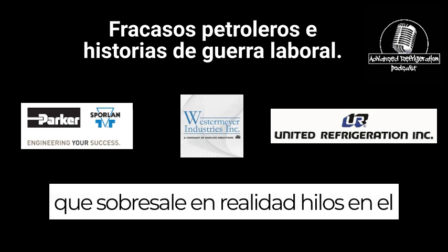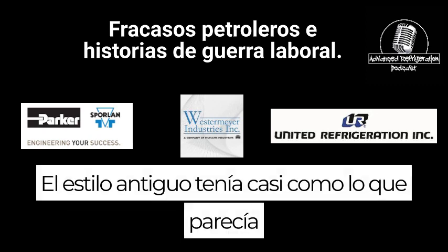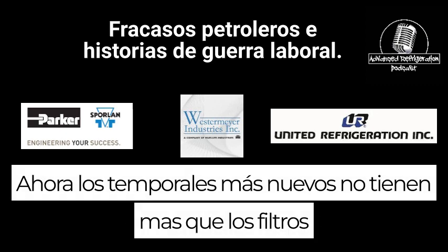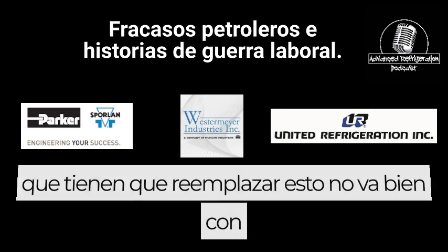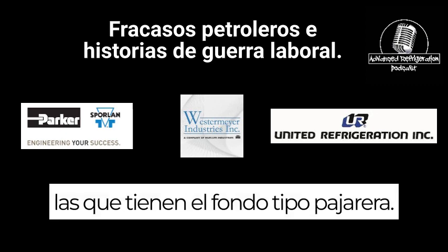Also be mindful on the Temprite oil separator on the older style of the actual piece that sticks up, that actually threads on the nut to enclose that coalescing filter. The older style had almost what looked like a birdhouse at the very bottom. Now the newer Temprites do not have that, but the filters that they have to replace this don't go well with the ones that have the birdhouse type bottom.